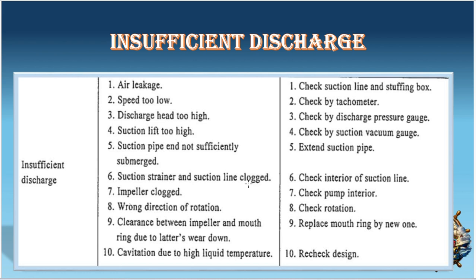Suction strainer and suction line clogged. Again, check the strainer, clean it. Impeller clogged, check the interior and make sure that the impeller is fully cleaned and taking the suction properly. Wrong direction of rotation. It is also possible. Rotation has to be checked and confirmed, and then accordingly the pump should run. Clearance between impeller and mouth ring due to the latter's wear down. Yes. Then in that case, the mouth ring has to be replaced with a new one. Nothing else. Cavitation due to high liquid temperature. Yes, in that case, we have to think, and either the liquid temperature has to be brought down, like suppose we are doing the transfer of some liquid, or wait for some time and prevent the cavitation. That is the main thing.